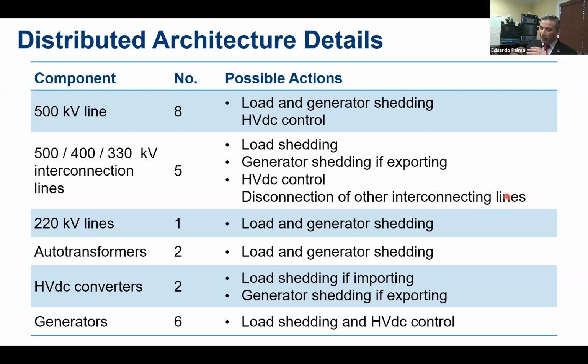But if you let this oscillation or this unbalance happen for a long period of time, if you don't catch it in milliseconds, then the system will eventually start oscillating and will not be able to be controlled. So we have to control in milliseconds, and when we're controlling interconnections, there is more importance to it. You know, it means the livelihood of other countries too. So there is one 220 kV line for load and generation shedding, as well as 2 auto transformers, 2 HVDC converters for load shedding if importing, generator shedding if exporting, and 6 generators.